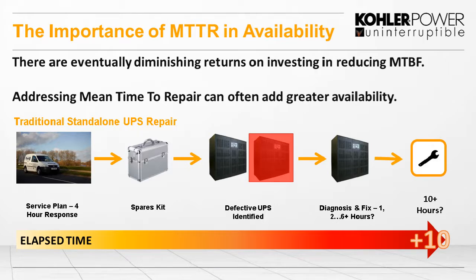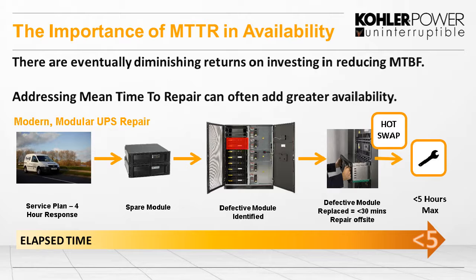But if we look at a modular UPS, again, the customer would give us a call, explain the issue, and if we believe that there was a definite problem with a module, we would bring out a complete spare module to site. And once we're on site, that will be swapped well under 30 minutes, typically a 10-minute swap on a modular UPS. Now that makes a big time difference on the MTTR.